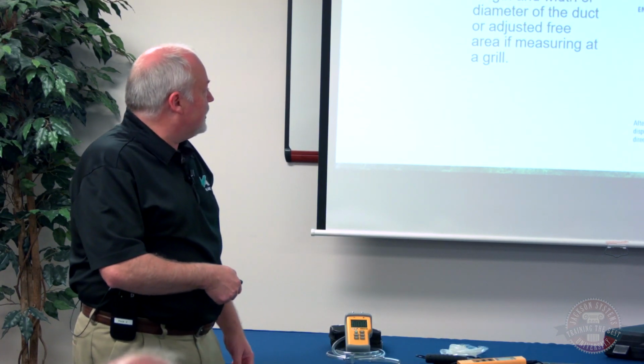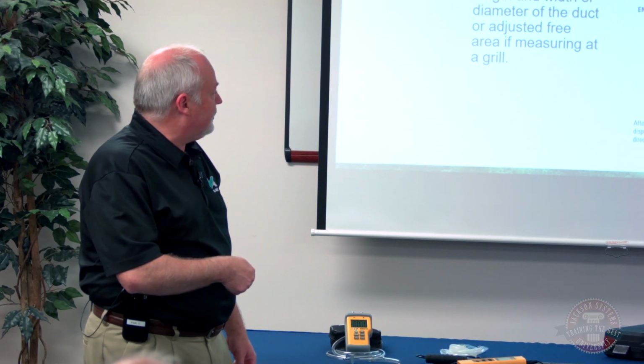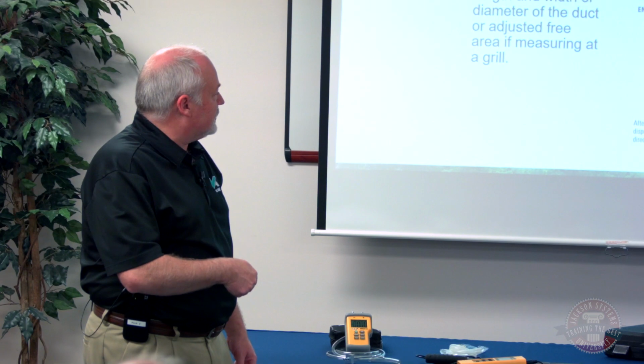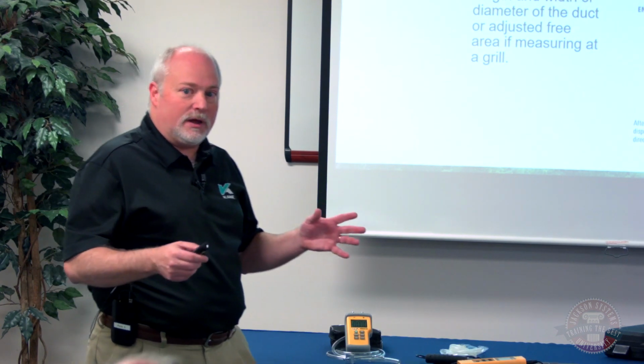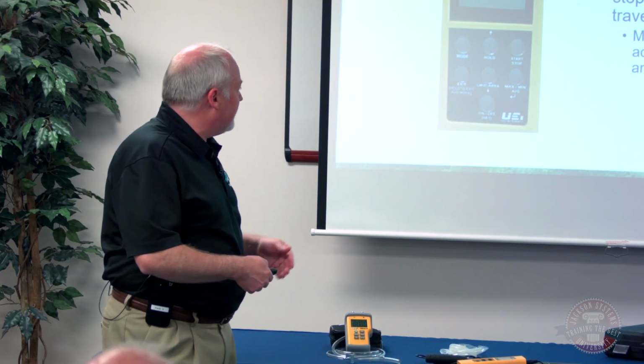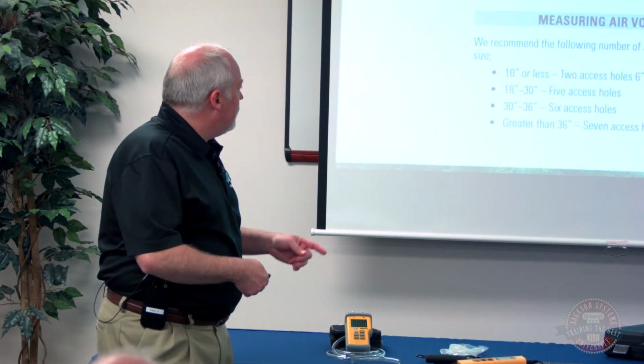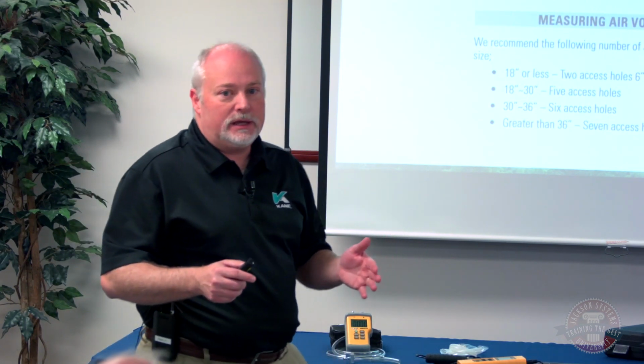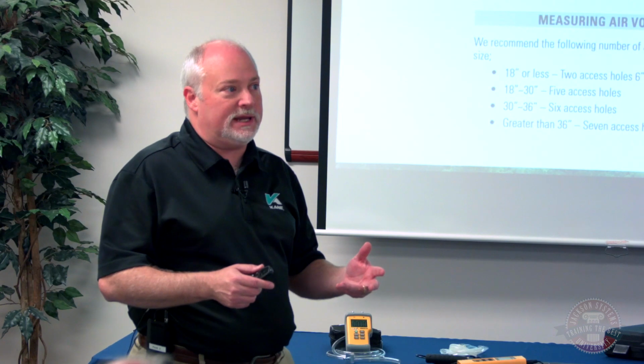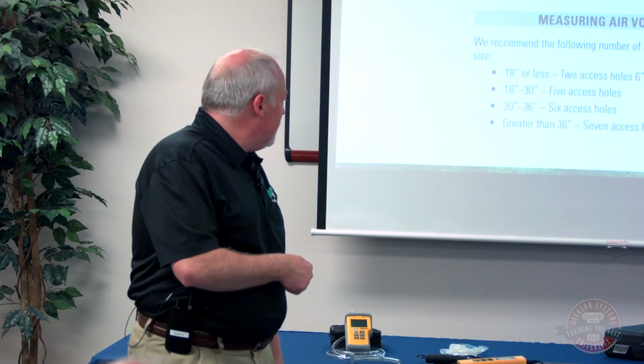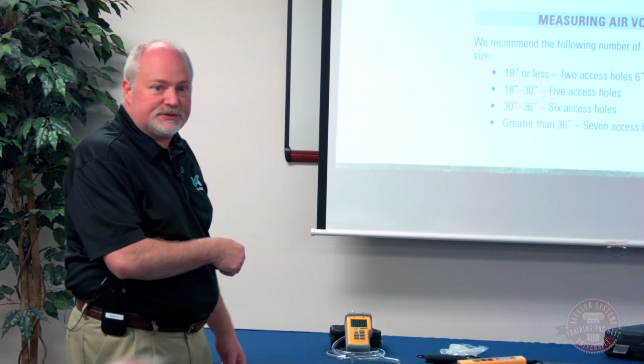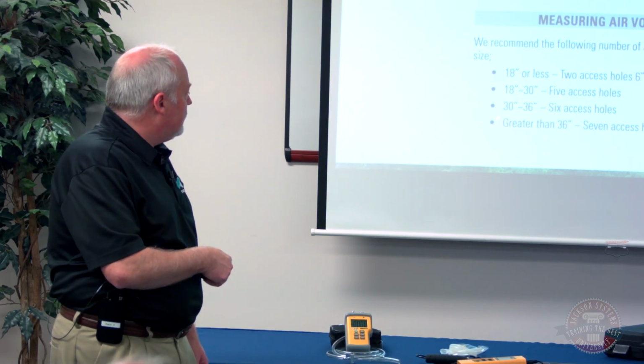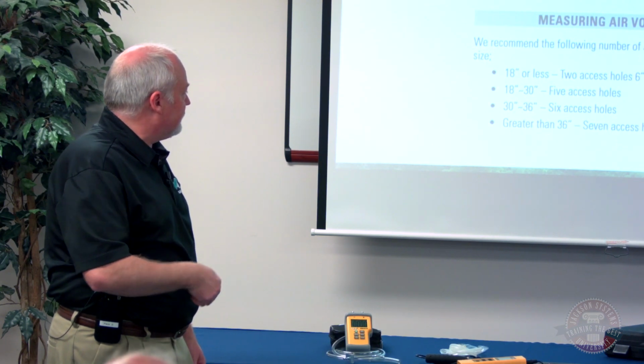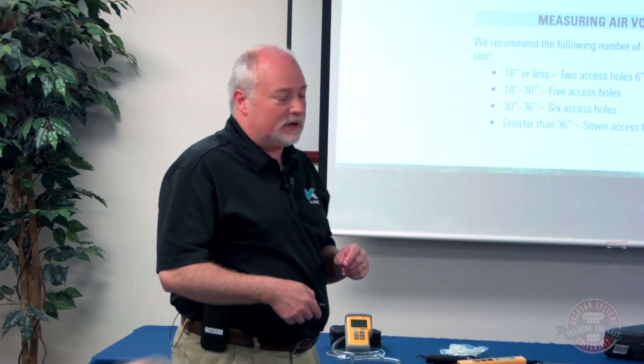Okay. So once we go into the mode, we're going to select either length and width or area. We're going to use our up and down buttons to enter that, get us a square cross section of what the area is of that ductwork. And then we're going to press our stop button so that we've got that ready. Okay. Depending on the size of our duct is going to dictate how many openings we need to get a good average measurement. If it's 18 inches or less, 2 holes, 6 inches apart. 18 to 30, 5 holes, 30 to 36, 6, or greater than 36, 7 access holes to get in to get a good average of that duct.